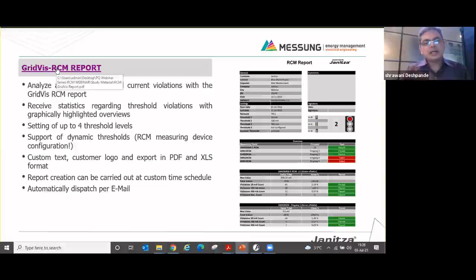I will take you to the RCM report. This is an RCM report that we can generate using GridVis software. Here we can generate this report over a period of one month. In individual machines, individual meters, we can set limits, that is a current limit, how much current should be passed, then we can get the threshold level, then we can get the alarm. Like that, we have set up threshold levels of current: 30 milliampere, 100 milliampere, 300 milliampere.